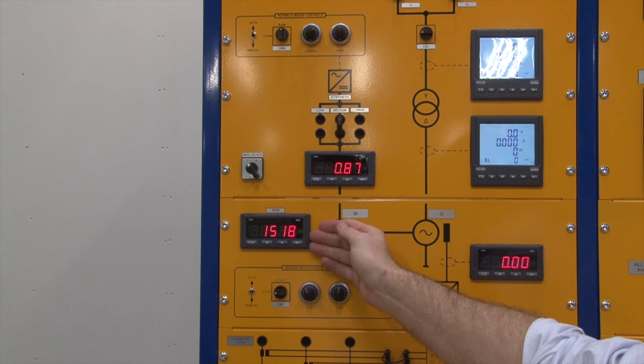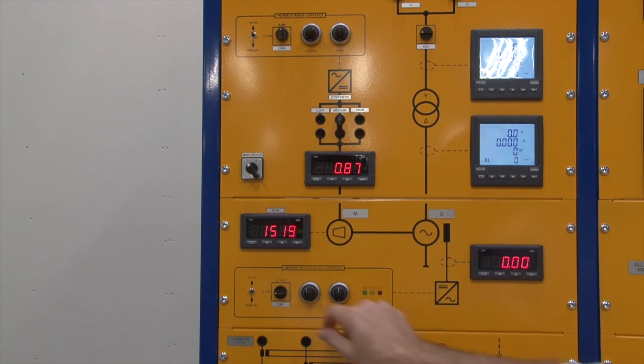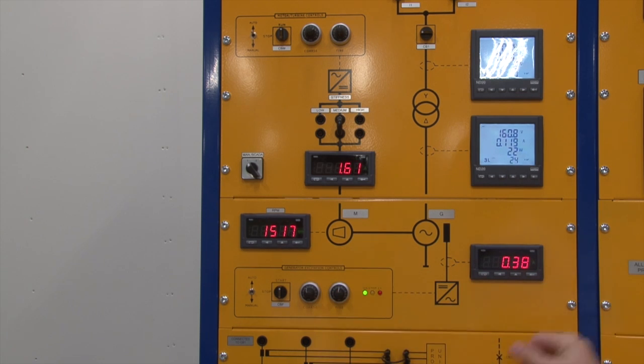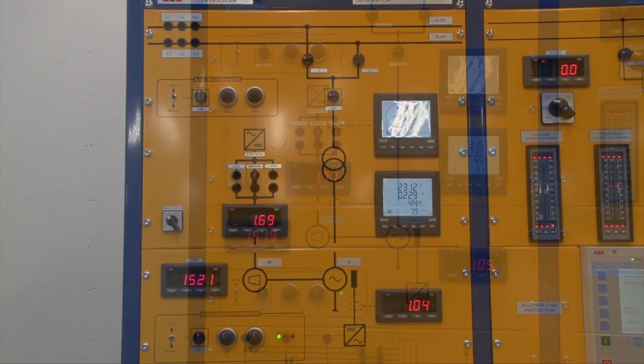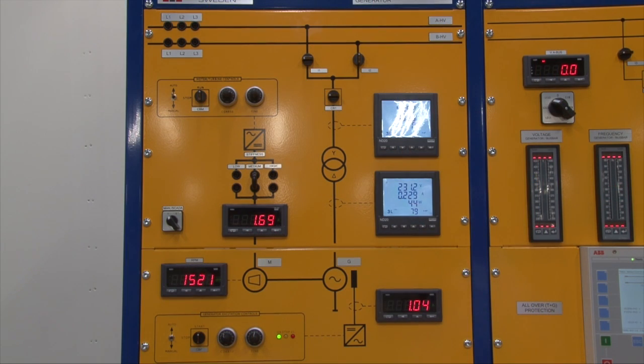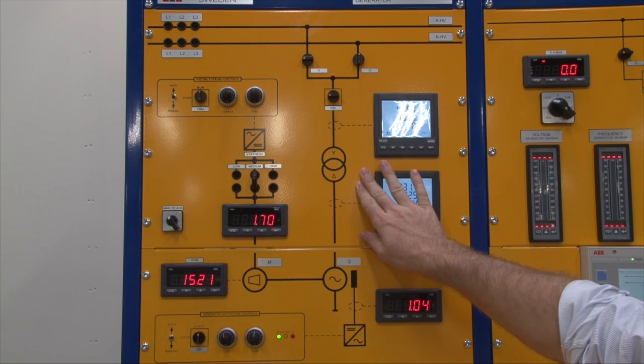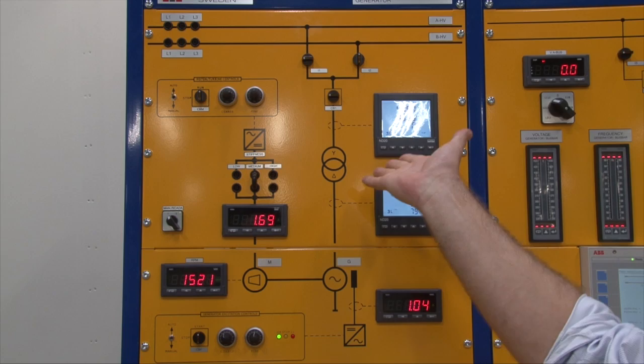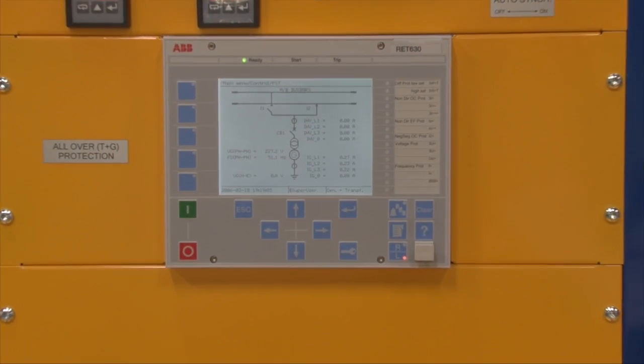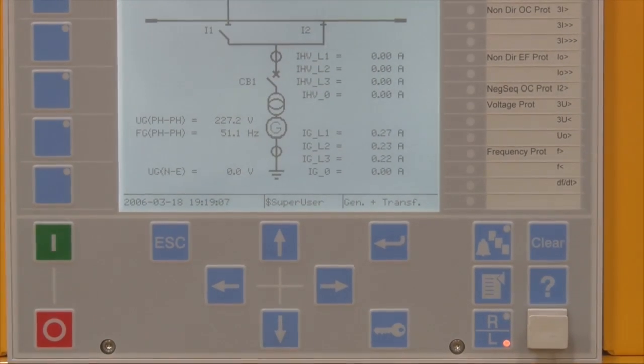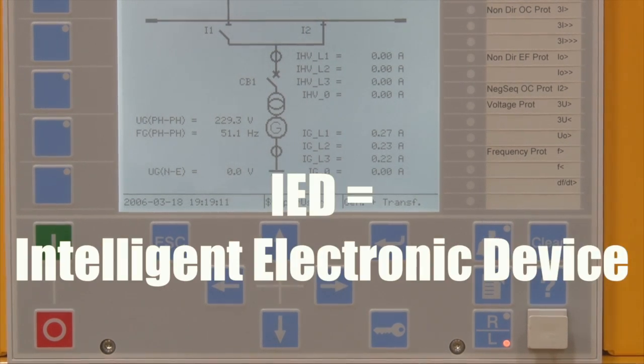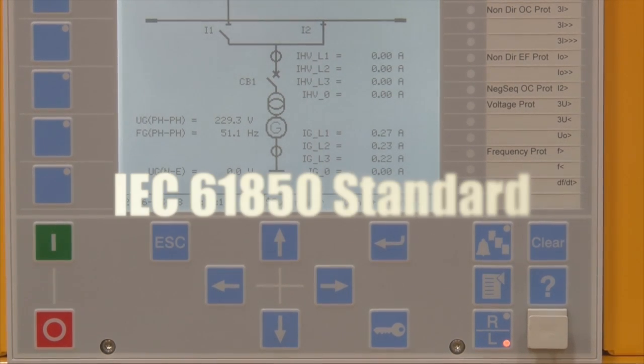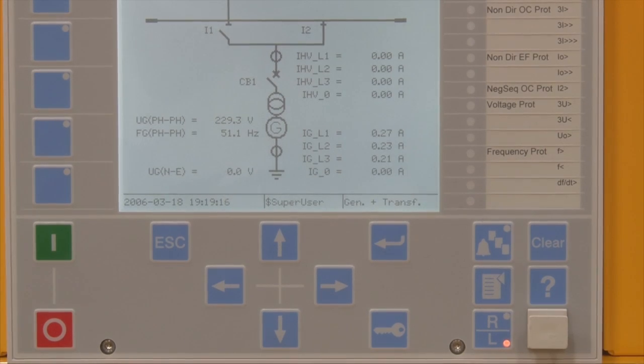With the prime mover up and running, we can then begin to generate power using the generator output controls. This generated power then undergoes transformation in a delta Y step-up transformer. This is done to counter transmission losses. Being vital, expensive and large components, the generator and transformer are both protected from fault situations by the latest IED relays, which comply to IEC 61850 standard for substation automation.